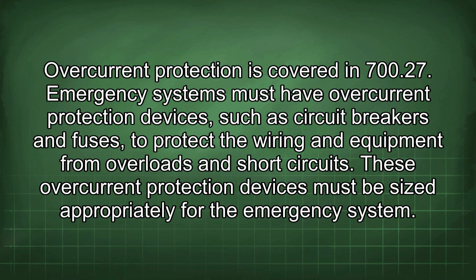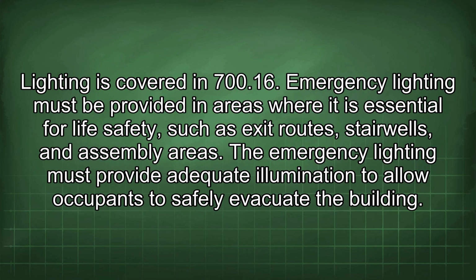Overcurrent protection is covered in 700.27. Emergency systems must have overcurrent protection devices, such as circuit breakers and fuses, to protect the wiring and equipment from overloads and short circuits. These overcurrent protection devices must be sized appropriately for the emergency system. Lighting is covered in 700.16. Emergency lighting must be provided in areas where it is essential for life safety, such as exit routes, stairwells, and assembly areas. The emergency lighting must provide adequate illumination to allow occupants to safely evacuate the building.